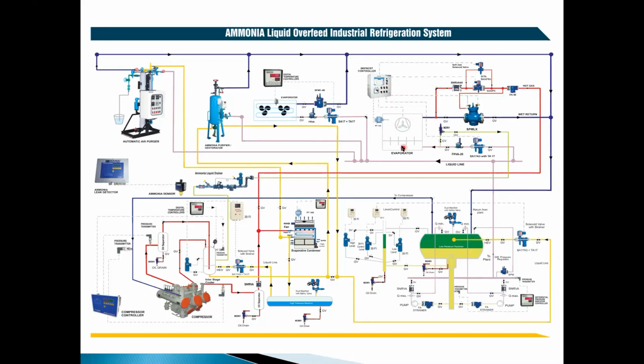Now the evaporator is at lower temperature, and the hot gas may be at say 80 degrees, 75 degrees. So what happens here is this gas starts condensing. It starts becoming liquid, and slowly the temperature of the evaporator starts increasing. Typically, when you reach a temperature of around 10 degrees, all the frost in the evaporator is melted. At the same time, the ammonia pressure also rises.